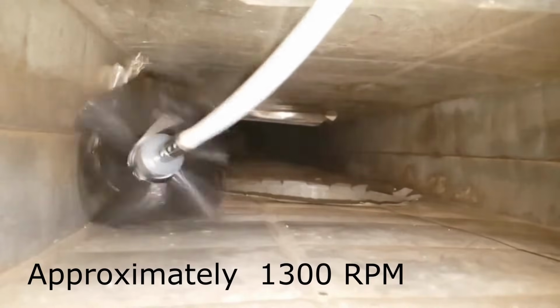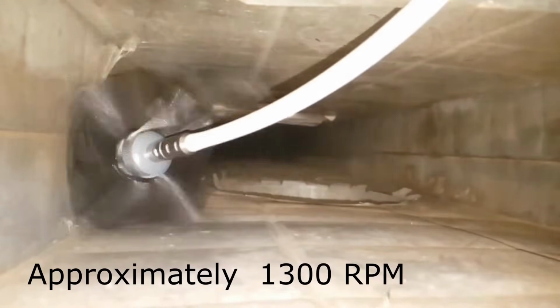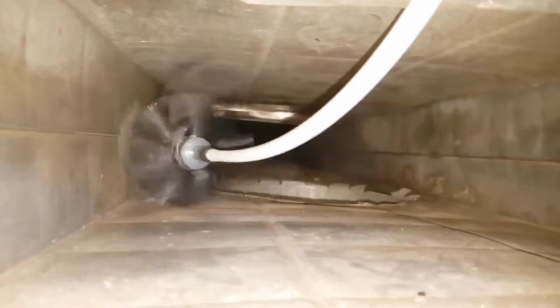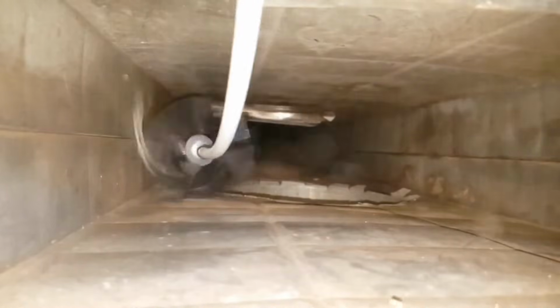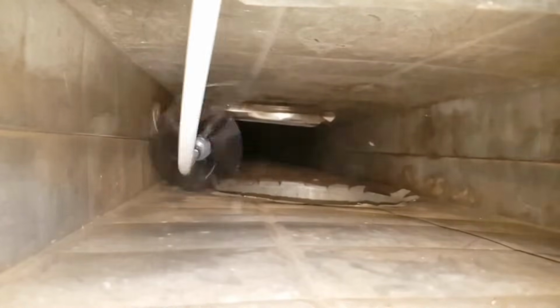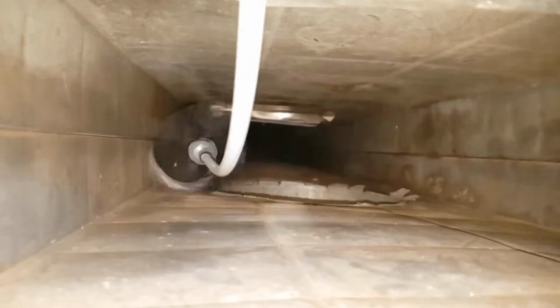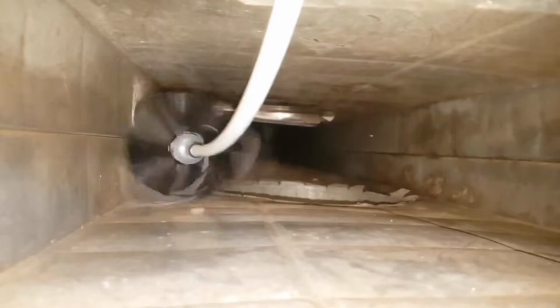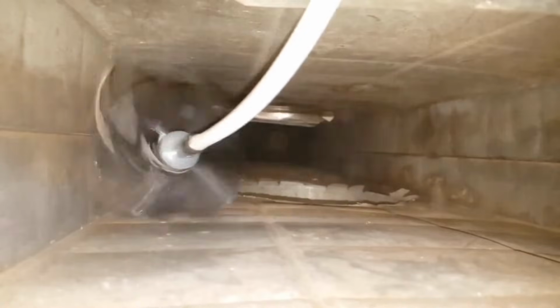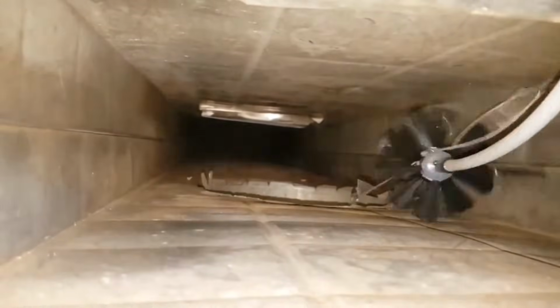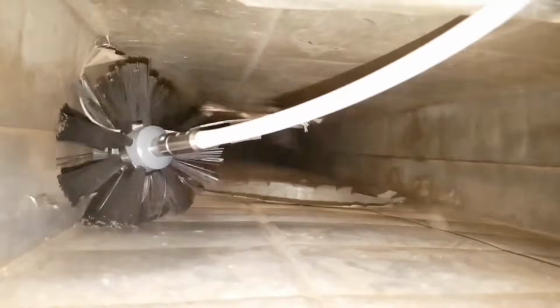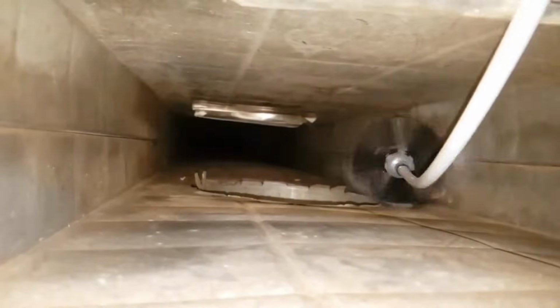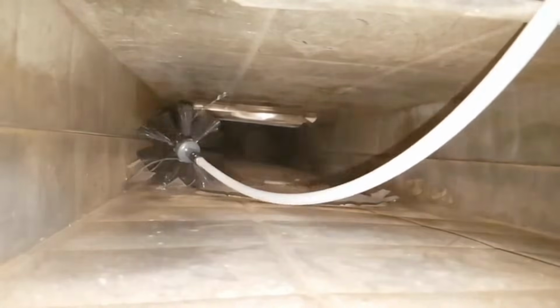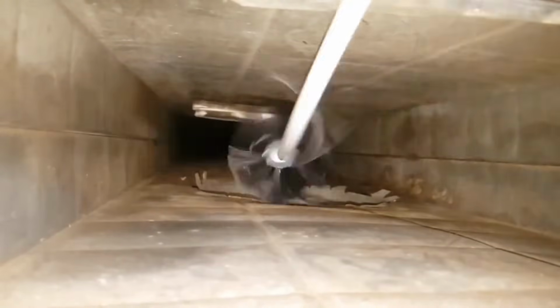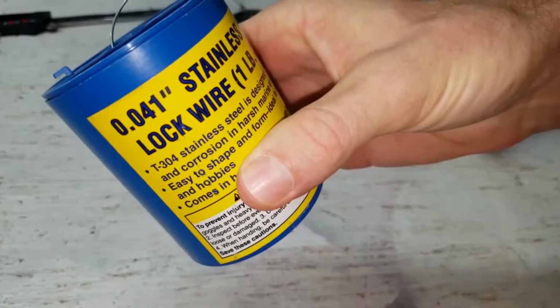I can tell from the sound that it's much more aggressive than the previous brush, not to mention more effective. It's cleaning the sides well, but not the center of this rectangle air duct. I have a DIY attachment that fixes that problem, which will be shown here in a bit. The bristles leave small scratches in the metal air duct, but residue is coming off. I don't want to see scratches though, because they'll just make the duct harder to clean next time. They may also promote corrosion in the metal ductwork, but they're very small, and there's a couple of nasty spots that I know are going to require thicker cable to clean.